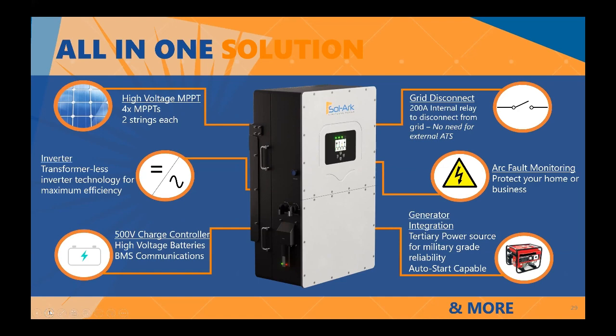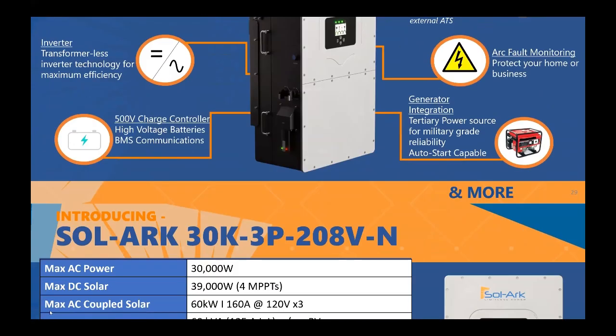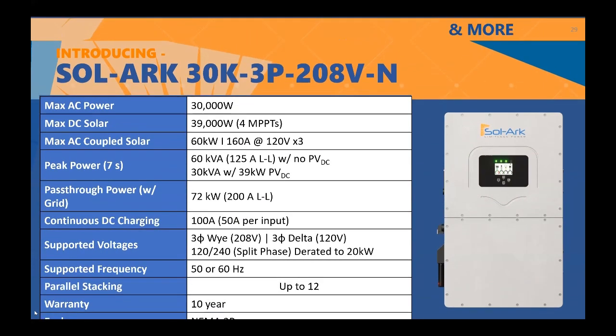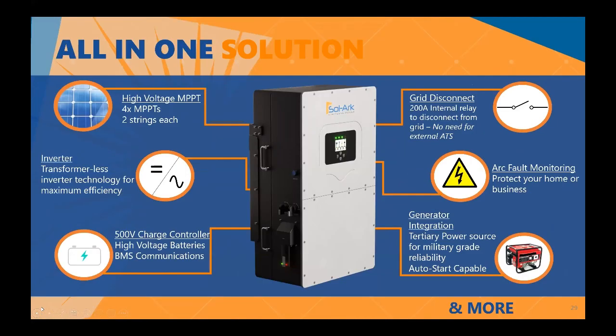And the last main aspect that we can see here in the slide is that we are a transformer-less inverter. Basically, we use IGBTs to convert the power coming from DC into AC. And again, guys, all of these features are available with our residential inverters. It's just a lot more power, more MPPTs, and the key difference of being a high voltage battery rather than a low voltage 48 nominal volt battery. But again, all of these same features are available in both the residential and commercial versions.